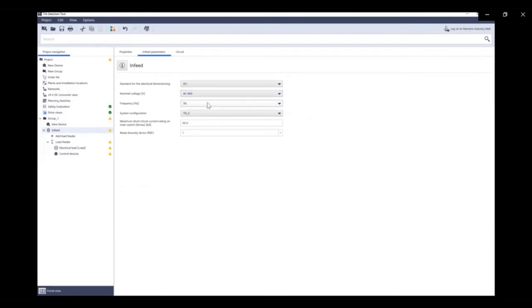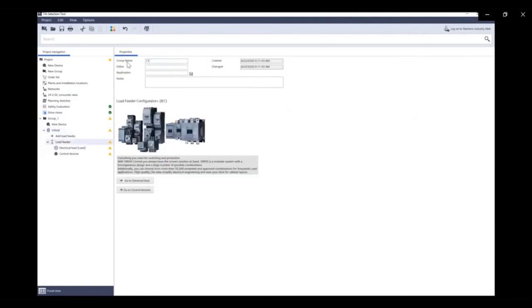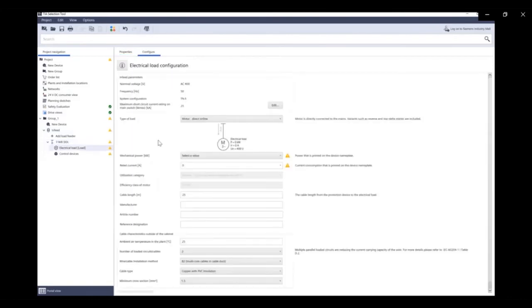I look at the value settings: voltage range, frequency, maximum short circuit current rating as it's applicable for my application, and rated diversity factor for the application. And I go into my circuit. So I rename the feeder to my example 11 kilowatts as a direct starter and go to my electric load. Cross-check on the data entered, looking into the value 11 kilowatts, 22 amps, this is the rating nominal current, change to the rating current, cable length of my application, ambient temperature in the plant.